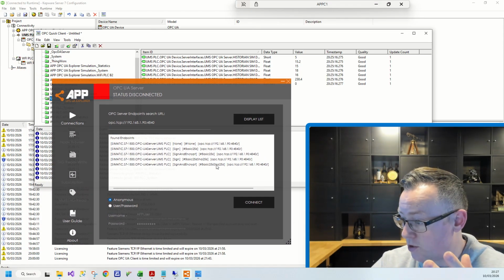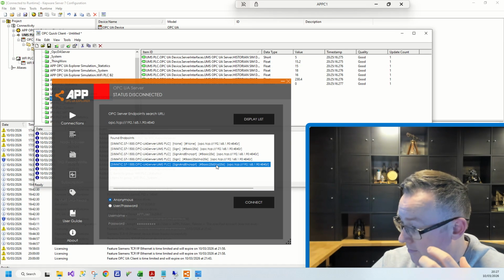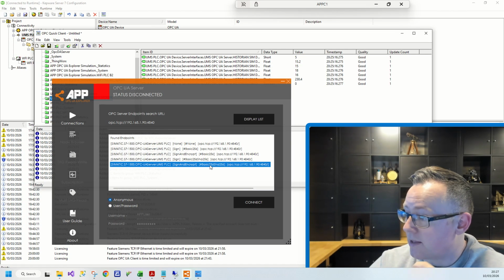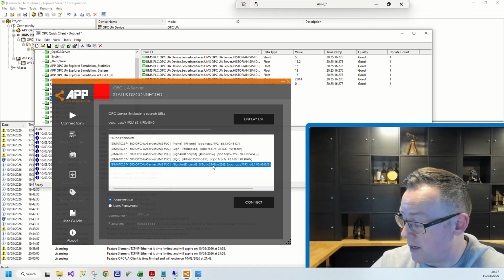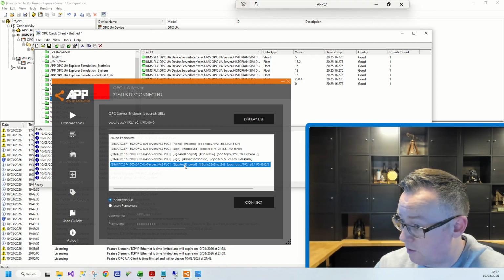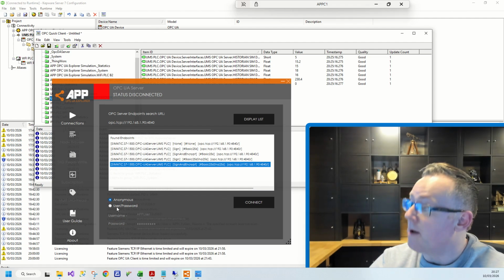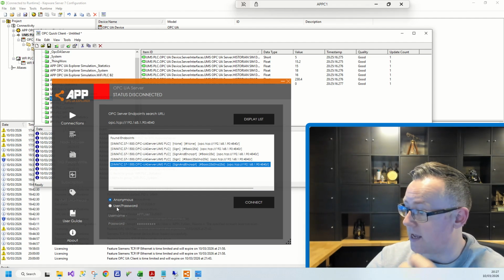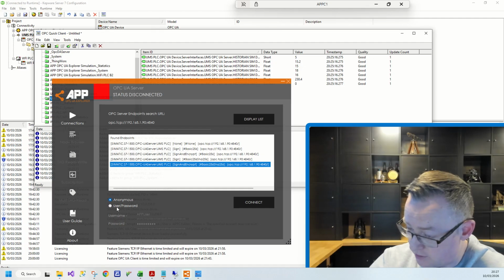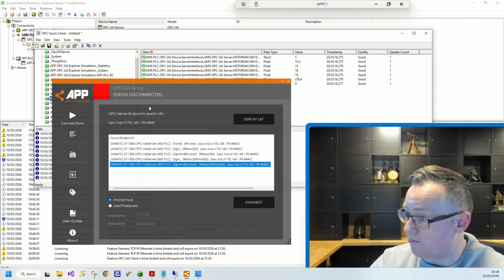I have all of these open channels, but in particular, if I had it locked down in the PLC, I have to use this encryption model here. I have to sign every time. All of the packets are encrypted when they go over the network, and I have to supply a username and password.